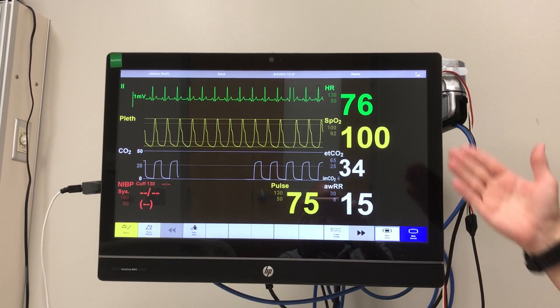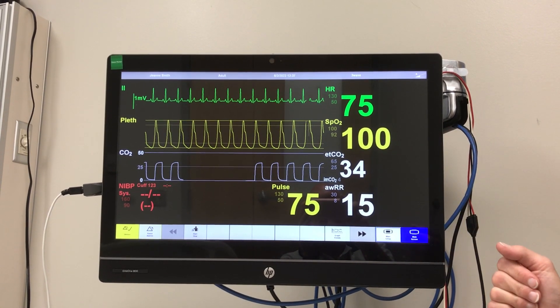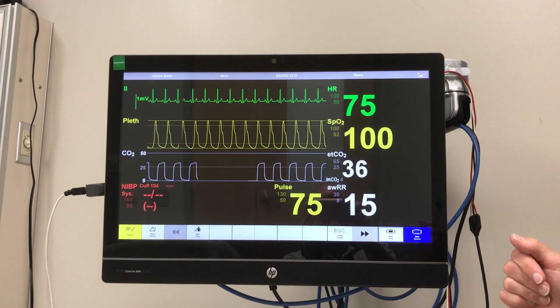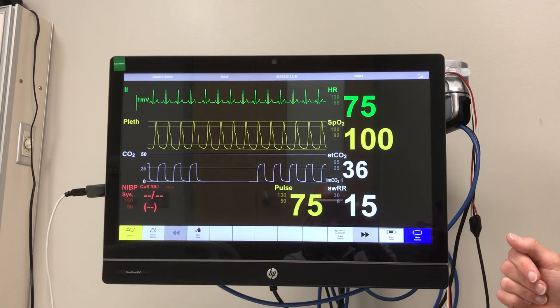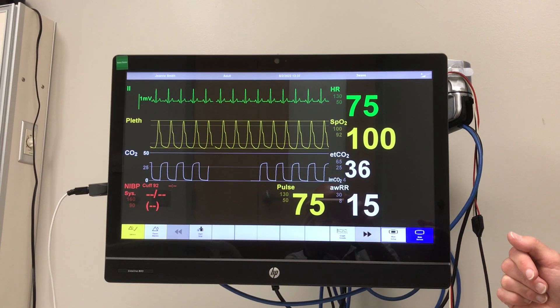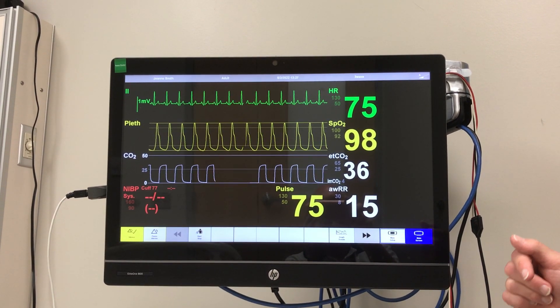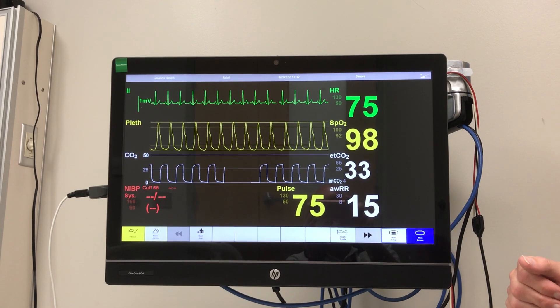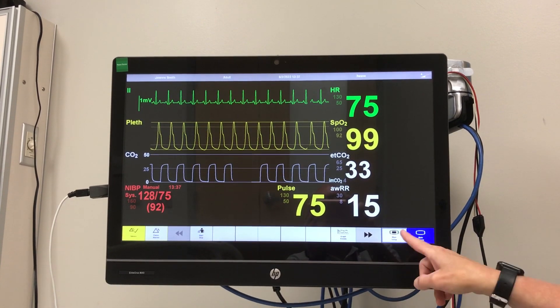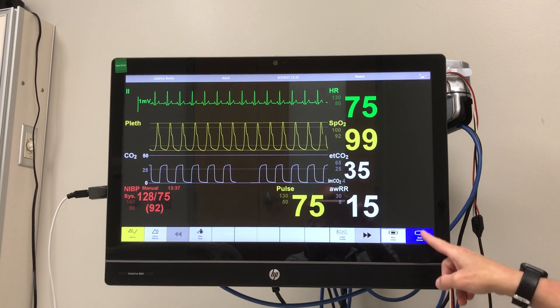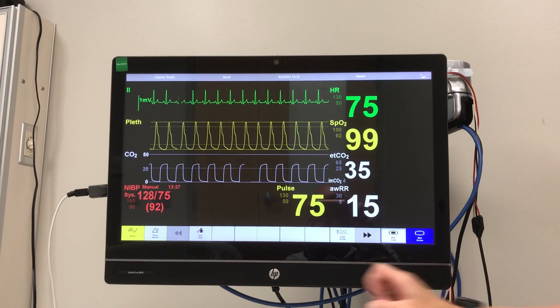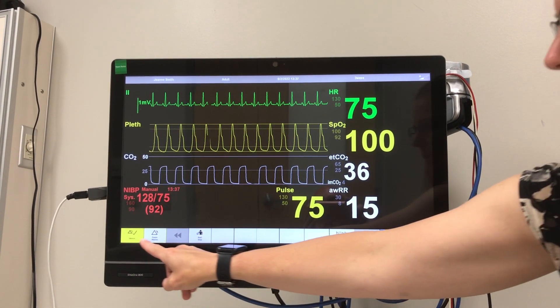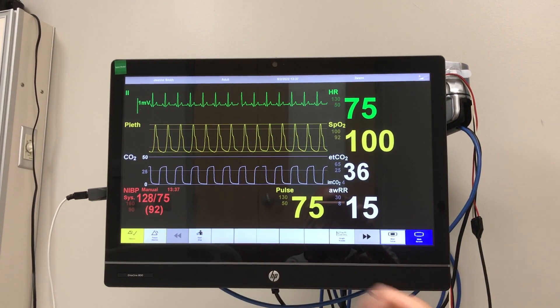That's pretty much how to run this functionality here. Once this gives me a blood pressure, I'll go in and show you how to set it to do an auto blood pressure every so many minutes, whatever you decide. Also on this screen, you have buttons here that give you main setup and main screen, and over here you have your silence buttons as well.